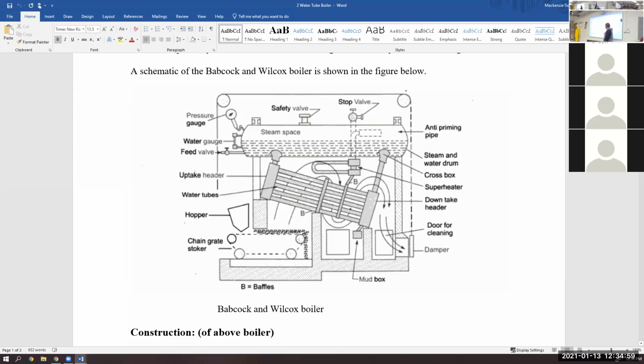We've got a superheater here, and a hopper where it comes in. This process of cleaning out the inside where the flue gases are is a very regular part of maintenance, because you get a ton of combustion products staying in that area. The more that film coats your water tube, the inside of your boiler, and the ignition chambers, the less efficient your system is.